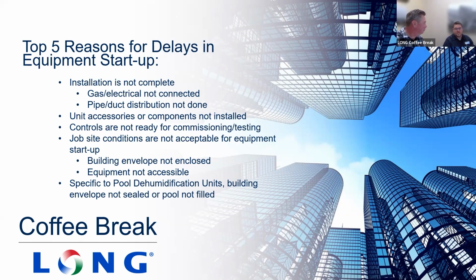Yeah. Specifically for PDUs, if we don't have windows, doors, water in the pool, certain components of the facility, and the adjacent space isn't isolatable from the space that the pool unit serves, it's hard to balance that unit and set that unit up appropriately. Yeah. So then we have a lot of return trips, and that creates more delays for everybody. I think at the end of the day, we're trying to start up the equipment in what's supposed to be the final state of the building, which, in today's day and age in construction, with equipment delays and doors and windows, the whole construction industry is in a little bit different spot than we're used to being in for decades previous.